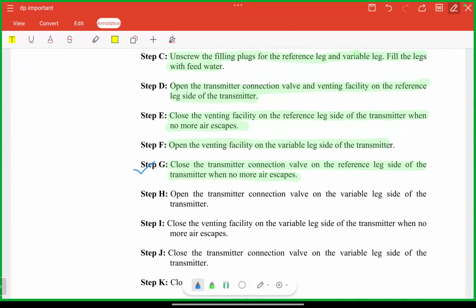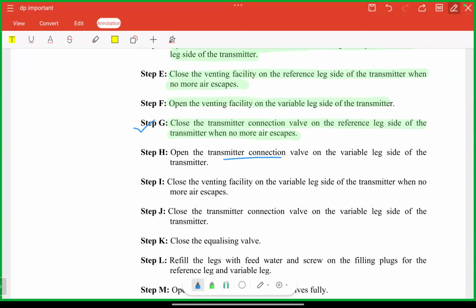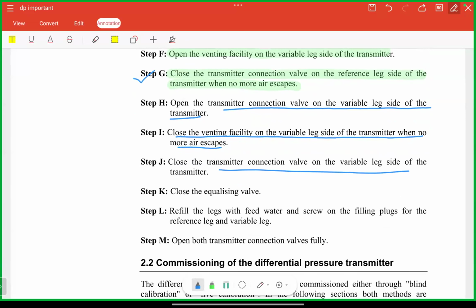Okay. Open the transmitter connection valve on the variable leg side of the transmitter. Close the venting facility on the variable leg side of the transmitter when no more air escapes. Okay, everything is here. The procedure for removing air has been explained. Okay, what is to be done next after that?